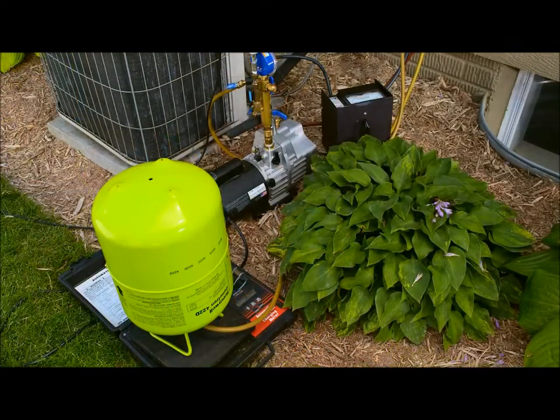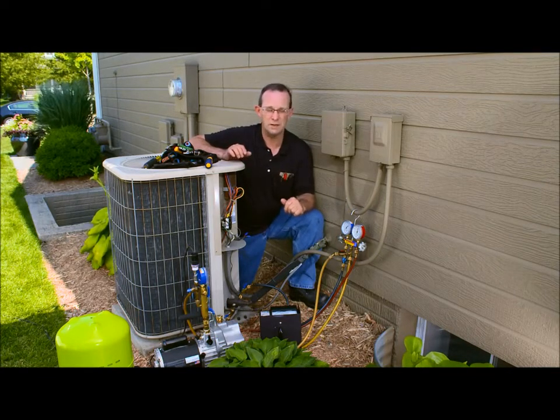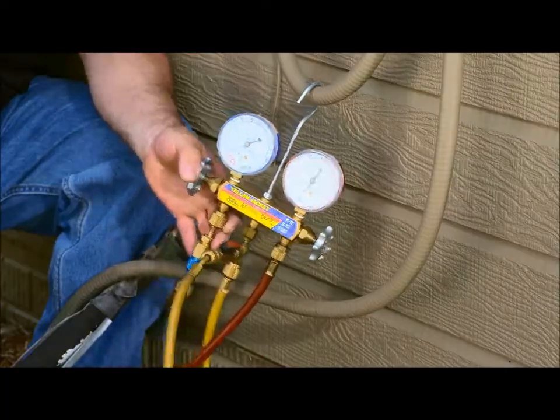When replacing R22 with Genetron R422D, use the same charging procedures that you would using R22. It's important to remember that R422D is a blend and we need to charge liquid from the cylinder into the system. I'm using a throttling valve on my manifold gauge to limit the amount of liquid that can go into the system. Charging too much liquid into the suction line can damage your compressor.